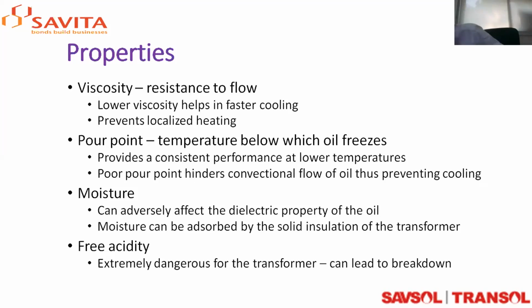Near the pour point, what is the viscosity of the oil, at what temperature does it gel? If the oil gels at an early temperature and the pour point is somewhat high, you will have to follow certain cold start procedures to run the transformer. This becomes most important when you take a shutdown and then restart the transformer. If the pour point is not good, you will have certain problems and will need to provide heating arrangements.